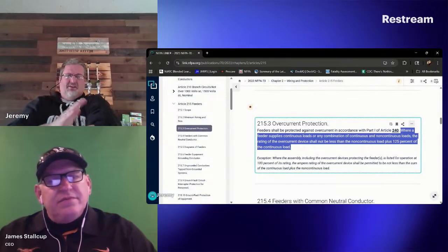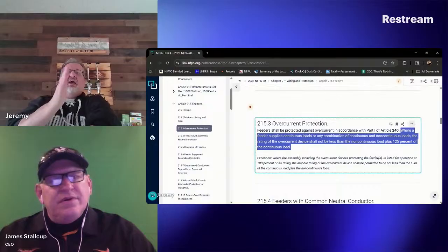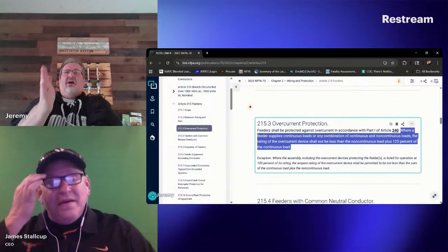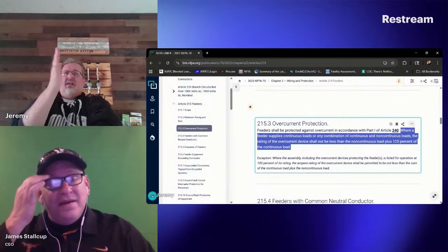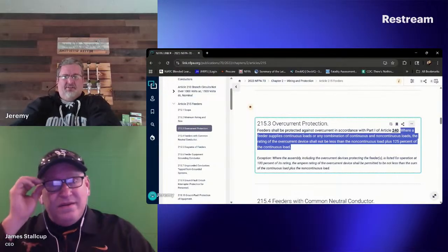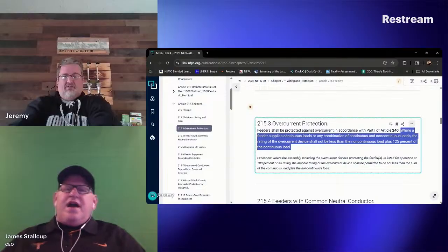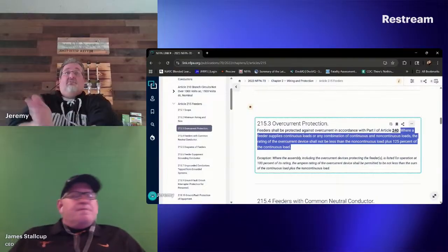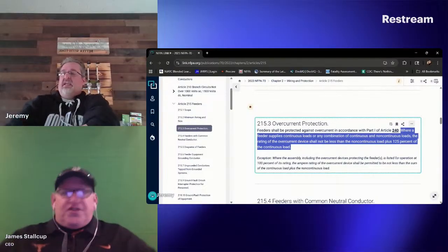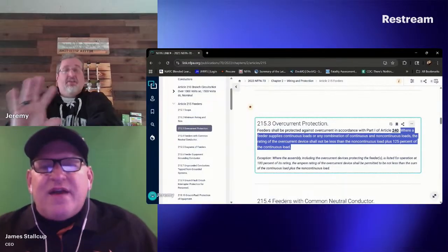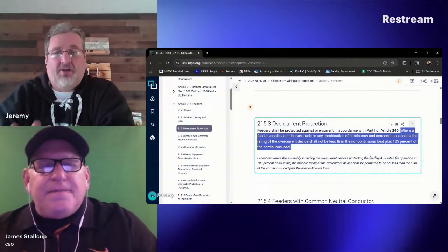No, hold on a second here. So you're saying that if I have a 100 amp wire, I cannot protect it at anything less than 100 amps? Say I calculate I've got a 98 amp load. Can I put a 90 amp overcurrent device on that? No. But thank you again. There's nothing in 240.4 that talks about a load.